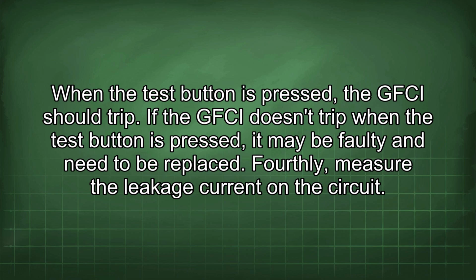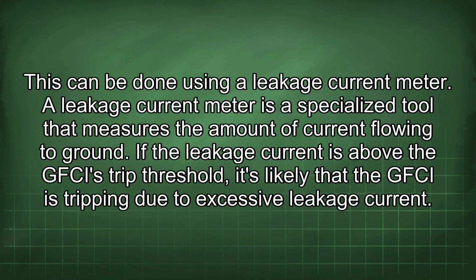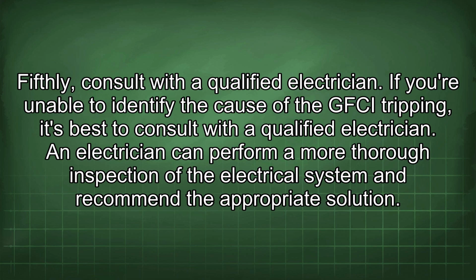Fourthly, measure the leakage current on the circuit. This can be done using a leakage current meter. A leakage current meter is a specialized tool that measures the amount of current flowing to ground. If the leakage current is above the GFCI's trip threshold, it's likely that the GFCI is tripping due to excessive leakage current. Fifthly, consult with a qualified electrician.